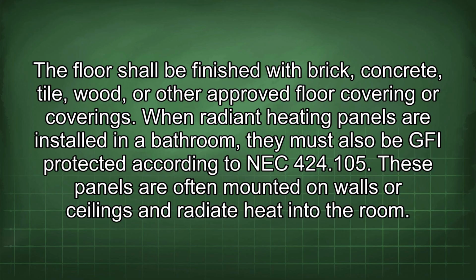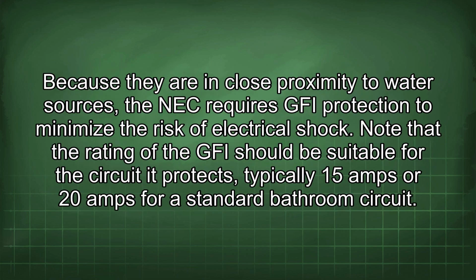When radiant heating panels are installed in a bathroom, they must also be GFI protected according to NEC 424.105. These panels are often mounted on walls or ceilings and radiate heat into the room. Because they are in close proximity to water sources, the NEC requires GFI protection to minimize the risk of electrical shock. Note that the rating of the GFI should be suitable for the circuit it protects, typically 15 amps or 20 amps for a standard bathroom circuit.